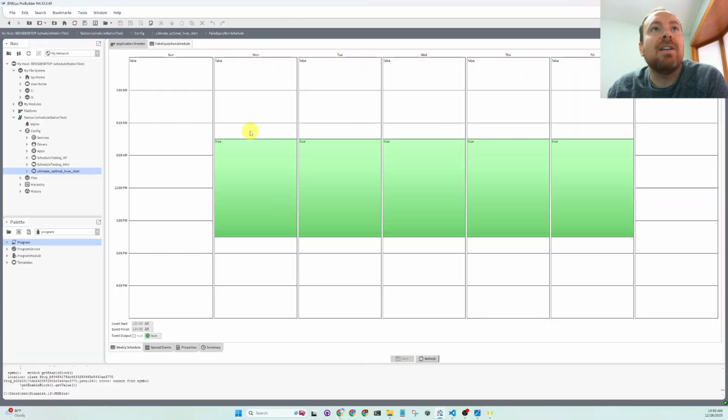There's another point that enables the block, otherwise this is always null. Then there's the maximum minutes allowed. Back in the schedule, there's a parameter that only allows a maximum, and I have it defaulted to 75 minutes. So if the models predict more than 75 minutes, it caps it at that. Then there's temp tolerance, and history days to retain, which is 14 days of performance history that we record. Here's our smoothing factor for EMA. This is actually just a delay parameter in here that I want to talk about in more detail.